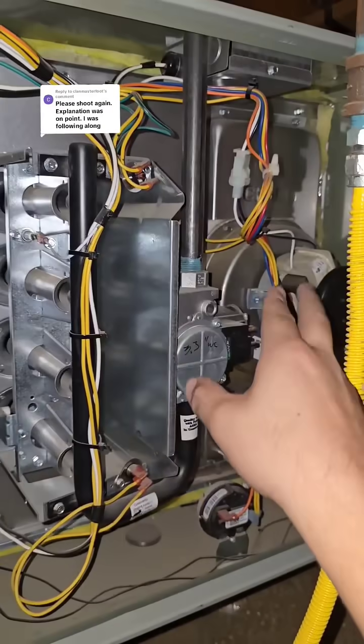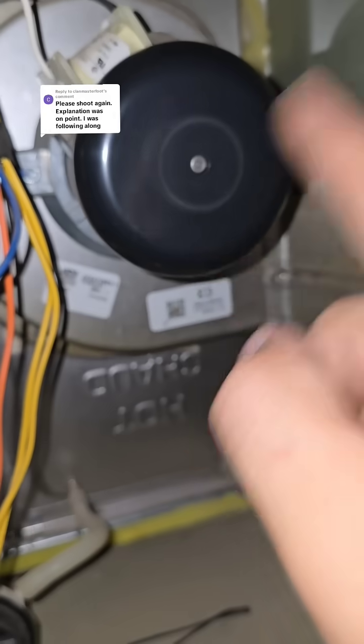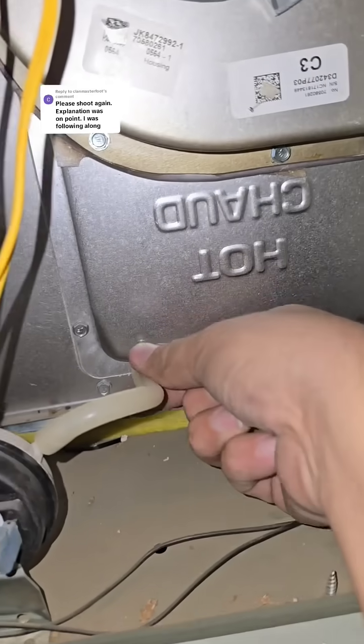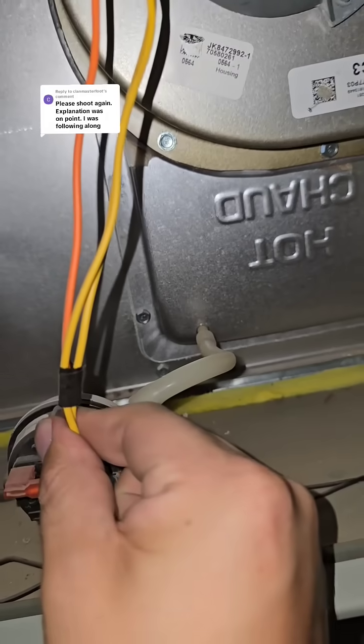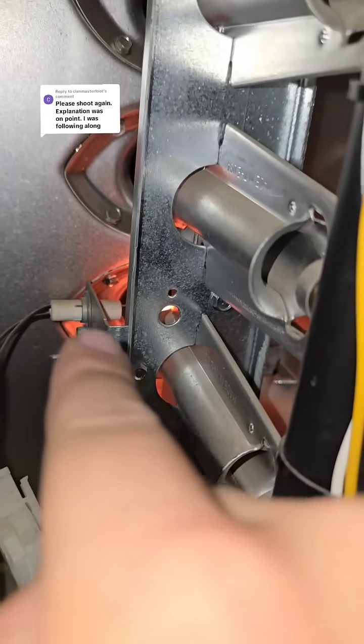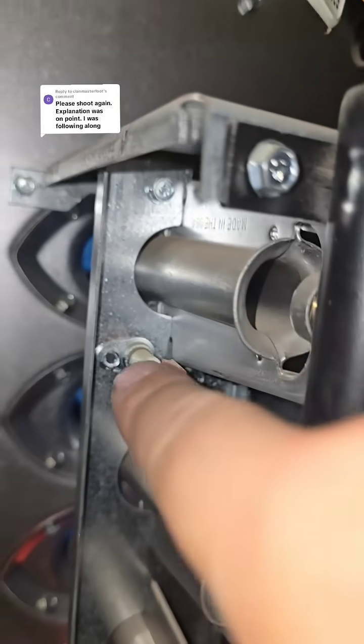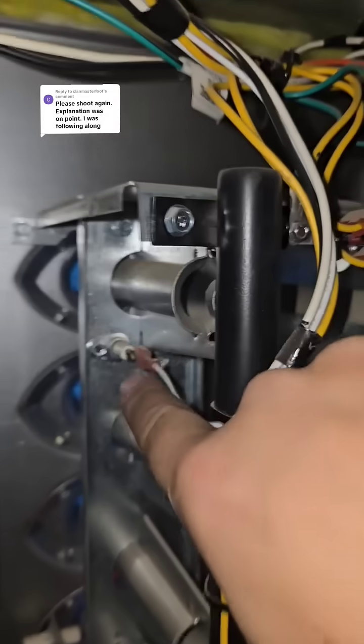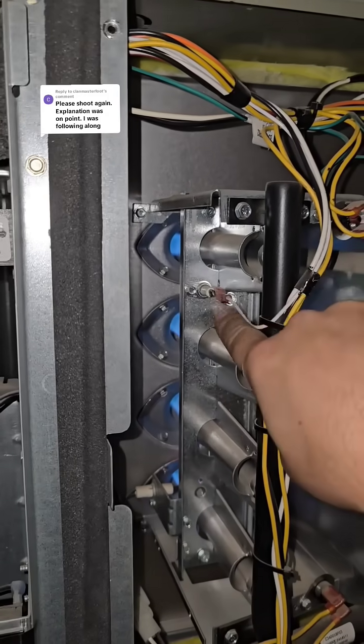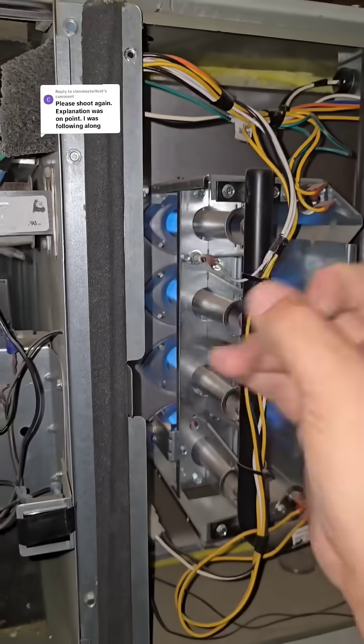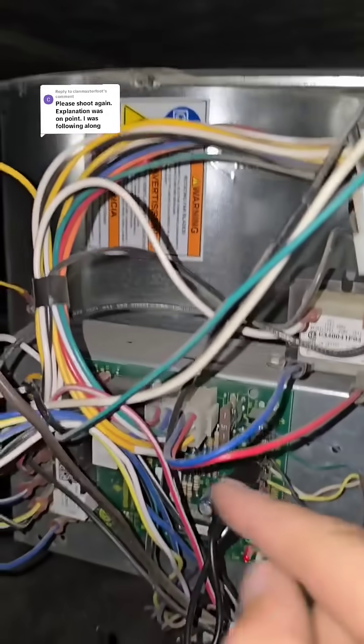You can diagnose these real easy if you know the sequence of operation. Okay, when I push this in right here, this inducer motor will start to spin. Once this inducer motor starts to spin, it'll pull pressure through this hose, closing these two wires. It'll go through all the safeties, and then this igniter will start to glow. Once this igniter starts to glow, then it's going to release the gas valve, and the flame is going to carry across. Once the flame carries across, it'll go to the sensing rod. The sensing rod will sense if there is a flame or if there isn't a flame, so it's not just spitting gas.